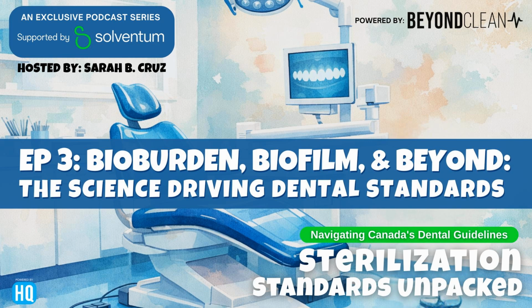It's the process challenge devices, and now there is a standard, 423, that has more information about how to make sure the process challenge device is suitable. Sometimes the process challenge devices are too challenging for a smaller sterilizer. So here we have to highlight following the instructions for use. For a smaller or tabletop sterilizer, the standards define whether the size, the volume inside the sterilizer, classifies it as a tabletop or as a regular bigger sterilizer. That will define maybe the type or part of the process challenge device used, but regardless, a process challenge device needs to be used.